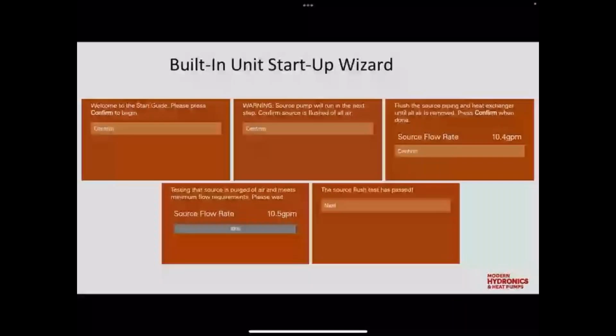And we've built a lot of stuff into this unit. So we have a built-in startup wizard, and these are just a few of the screen pictures from that unit. I don't really have enough time here to go through all of them, but I just wanted to show a little bit of what you can expect the first time you power this unit up. I get the calls quite often. People want to fill and flush the machine before powering it up. And we actually want you to power the unit up because the screen will walk you through the filling and flushing steps, and the motorized ball valves that are internal to the machine. You can operate them right from the screen.